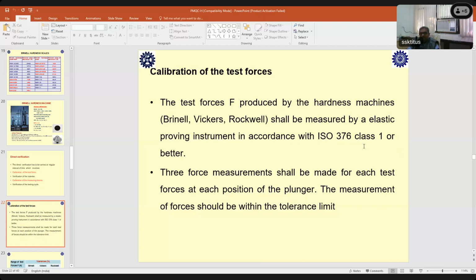So you can use load cell based machines instead of even dead weight machines, and this force verification has to be done using load cells. And this force verification has to be done at different levels also. Normally, as we calibrate these UTMs and the other machines, we have to follow a somewhat similar procedure, but it is not exactly as per 1828.